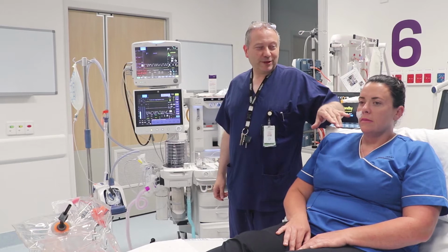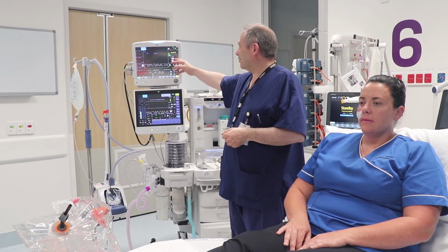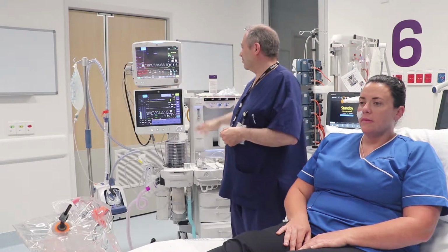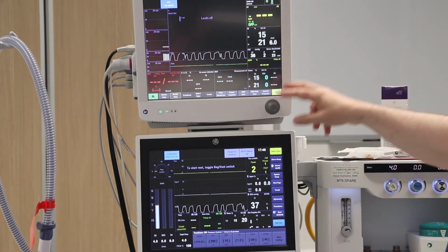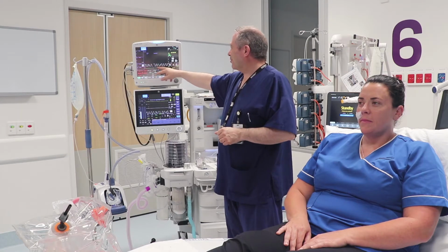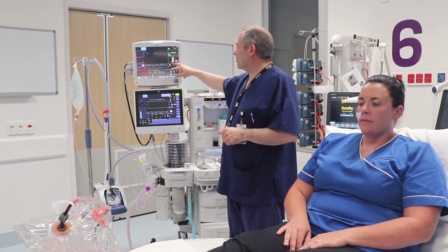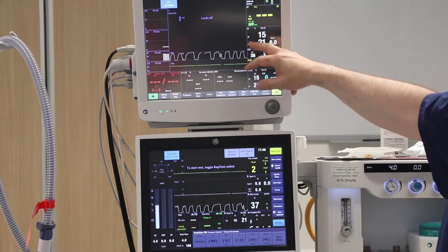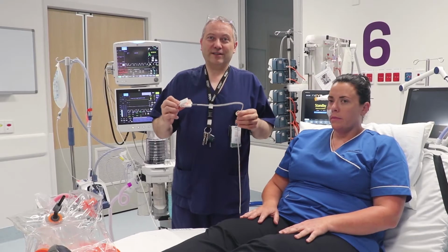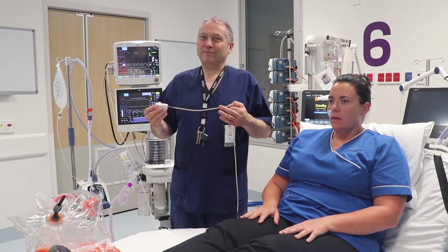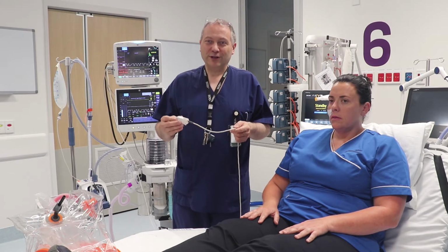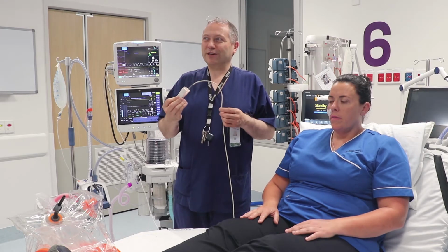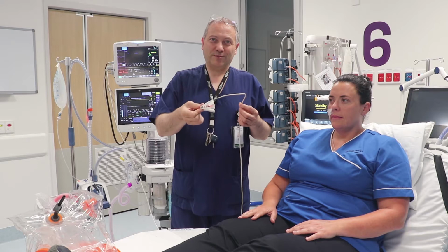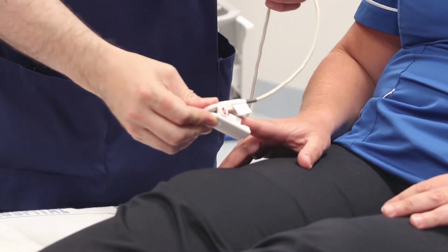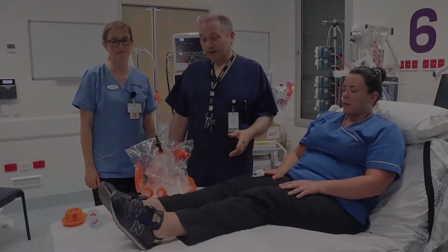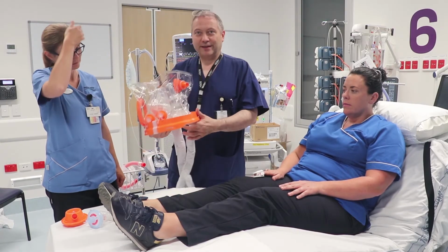So at the moment, the capnography tube is being monitored through the monitor up here, which we've got on an anaesthetic machine set up. But as well as the capnography and the capnograph trace, we also have the inspired and expired oxygen concentration being displayed in the digit field. Now, for safety, whenever you're using CPAP or a helmet CPAP and you're unfamiliar with it, you should always apply as much monitoring as possible. So we would recommend an ECG, and as an absolute minimum, a saturation probe that will monitor the oxygen saturations and heart rate. So the next thing we're going to do is apply the helmet.